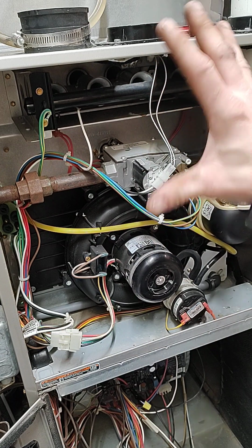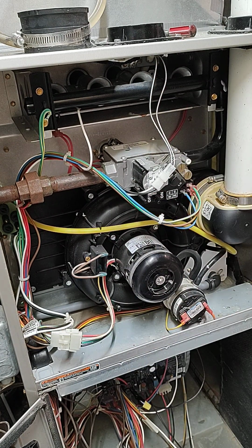This thing is blowing air out and it needs air to replace it. So if you add a wood stove, make sure you have either another pipe downstairs you can put a motorized damper on, or—what a lot of people do, and it's building code here in Wisconsin—you run a 6-inch pipe outside with a hood, and then pipe that into your ductwork.